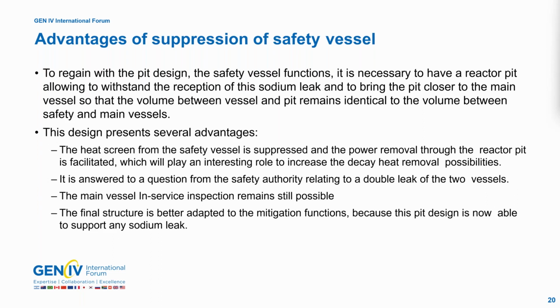What are the advantages to suppress the safety vessel? If we arrive to have a pit designed to take the safety vessel function, we can suppress the safety vessel, and we can maintain the function of having a volume between the pit and the main vessel. The design presents several advantages. The heat screen from the safety vessel is suppressed, and the power removal through the reactor pits is facilitated. And so we'll see that it's interesting to increase the decay heat removal possibilities by the pit circuits.